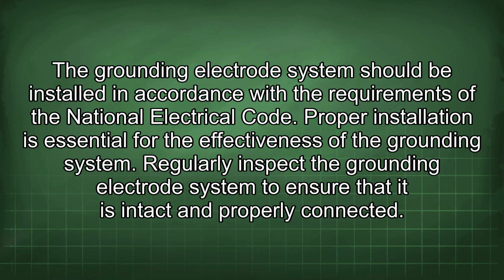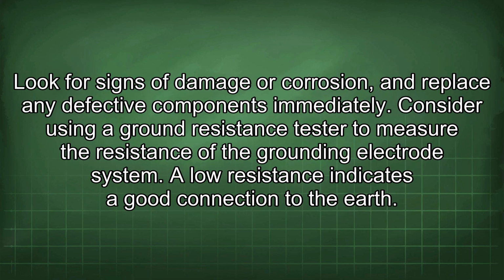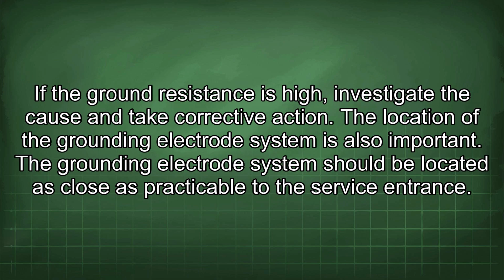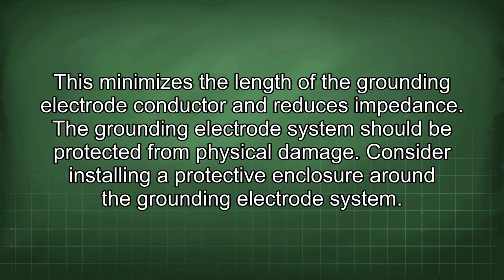Regularly inspect the grounding electrode system to ensure that it is intact and properly connected. Look for signs of damage or corrosion and replace any defective components immediately. Consider using a ground resistance tester to measure the resistance of the grounding electrode system. A low resistance indicates a good connection to the earth. If the ground resistance is high, investigate the cause and take corrective action. The location of the grounding electrode system is also important. The grounding electrode system should be located as close as practicable to the service entrance. This minimizes the length of the grounding electrode conductor and reduces impedance.